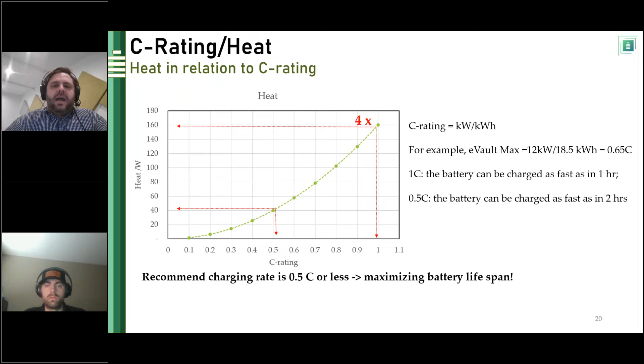So what it really comes down to is heat. No matter how you cut it, even if the battery is rated for 1C, it's going to generate more heat when it's discharged at a faster rate rather than at a slower rate, and that will ultimately lead to cell degradation. So at any rate, if it's a 2 E-Flex installation with 1 Sol-Ark, it is possible to configure the settings so that the batteries charge at a slower rate, but still can discharge at the fastest rate possible during a power outage. Maybe you want to look at your grid sell back and say, hey, if I have a 5-hour window for time of use arbitrage, I don't need to sell back at the 1C rate. I can sell back at C/2 or even slower than that if I'm really interested in having a battery that will last over a decade.